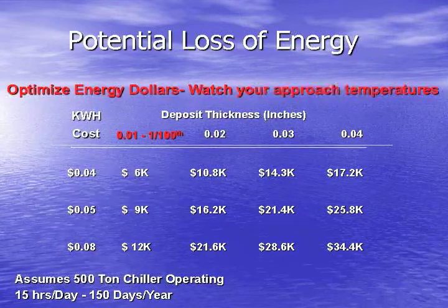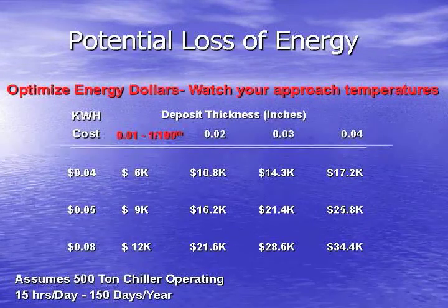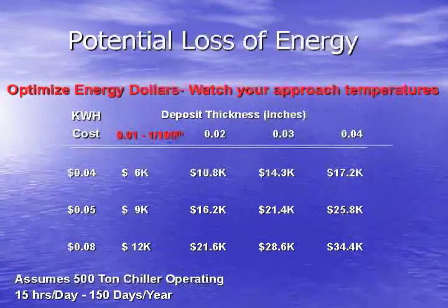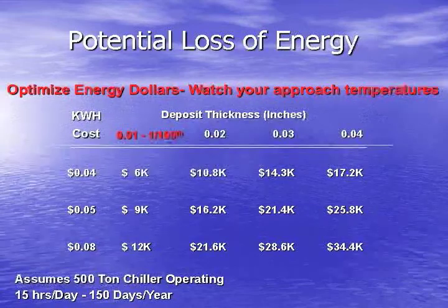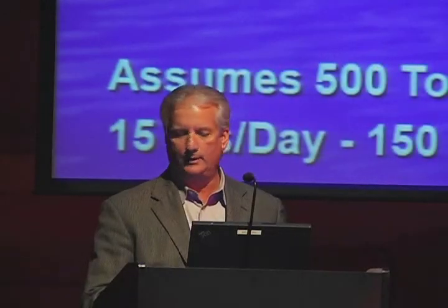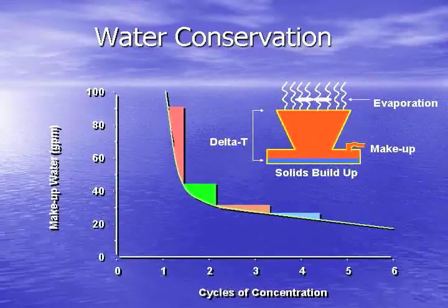So, for example, if you had a 1/100th of an inch of scale, now that's about a thumbnail thickness or less of scale formation, assuming you have a 500-ton chiller operating 15 hours a day, 150 days per year, which might not be too off of what you guys do up here. Depending on the KW cost in the area, you could lose anywhere from $6,000 to $12,000 annually in electrical costs just by having a small film of deposition on the tubes.